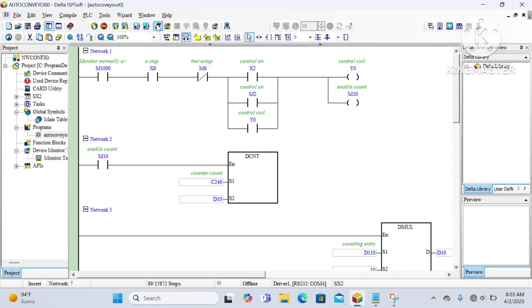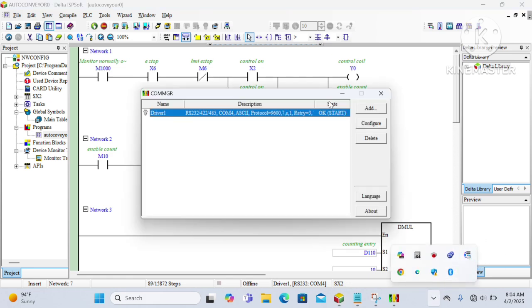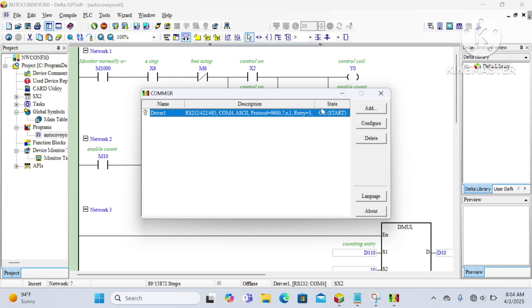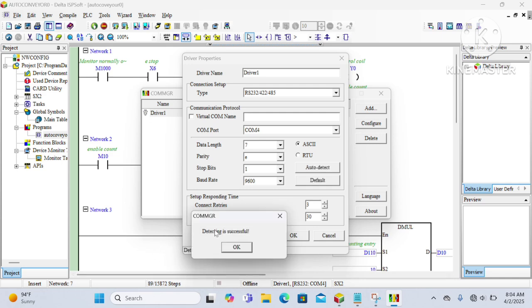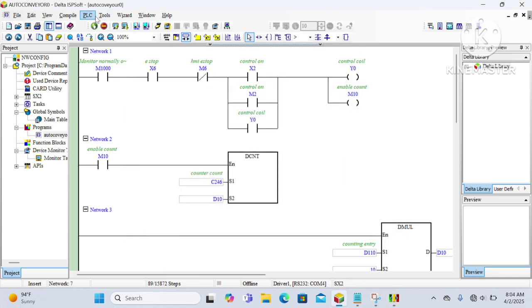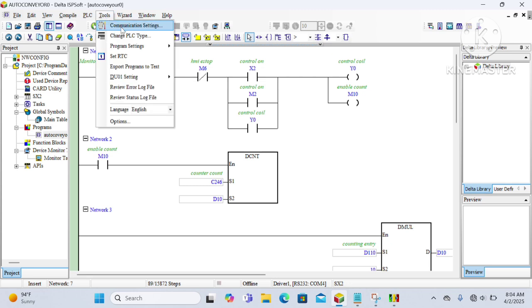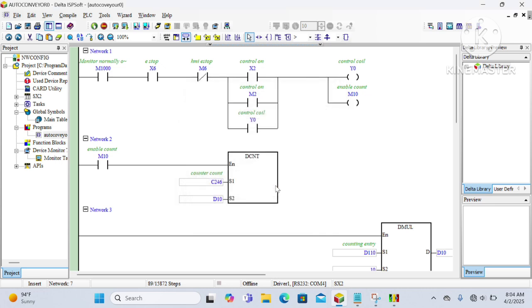Before downloading, we should check the communication from the COM manager. You can find the COM manager at the bottom. From here we enable it, open it, and you can auto-detect your device — I'll use auto-detect and wait for feedback. If successfully added, it will show that detection is successful. Now we can communicate with the PLC device. We confirm communication from the tool — Driver1 is already set, so now we can download the program to the PLC.